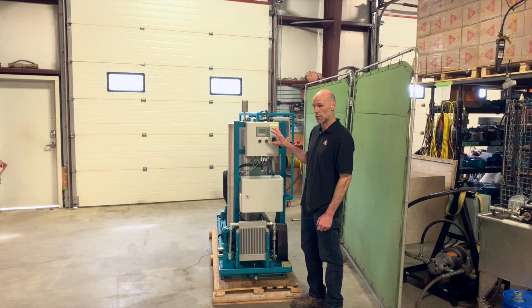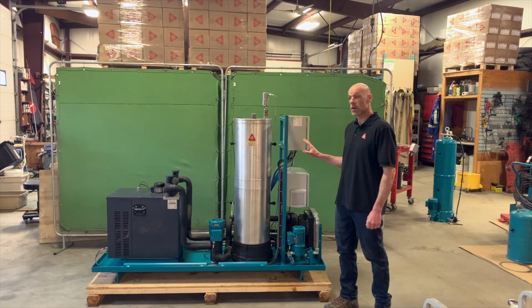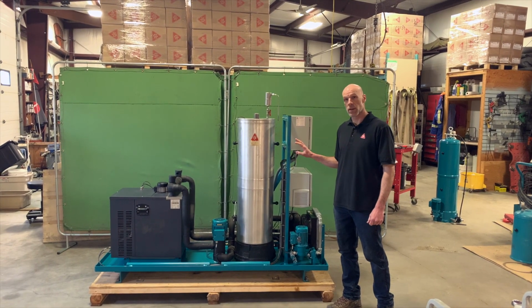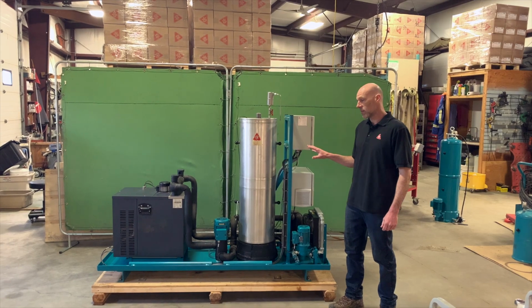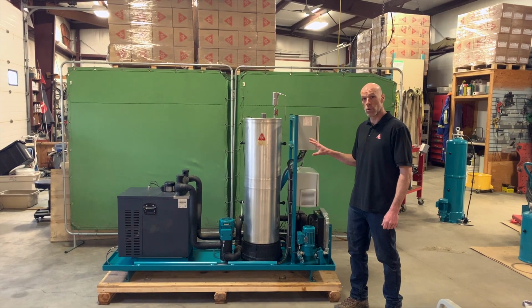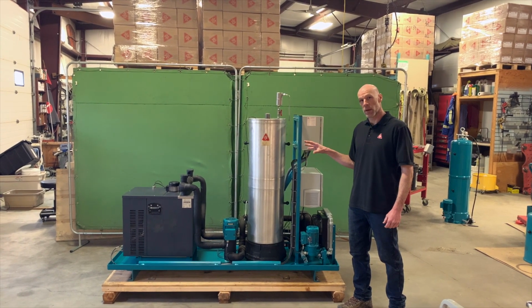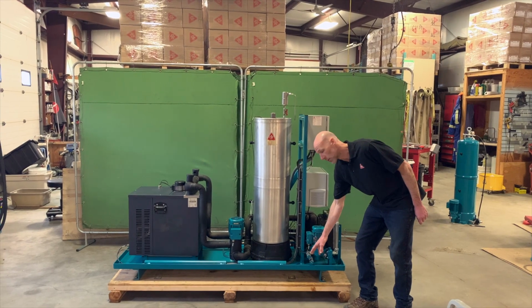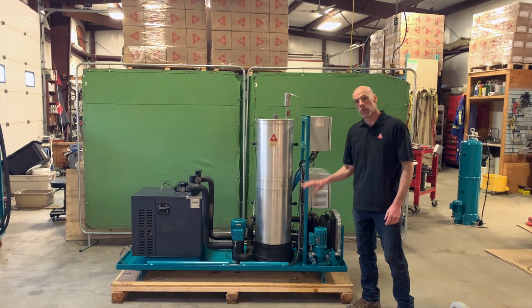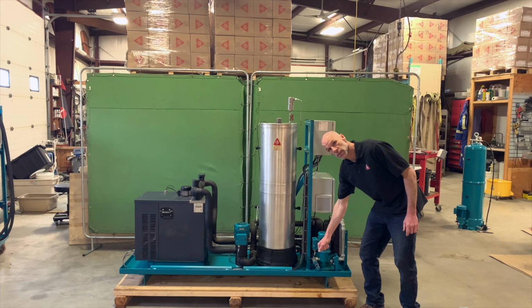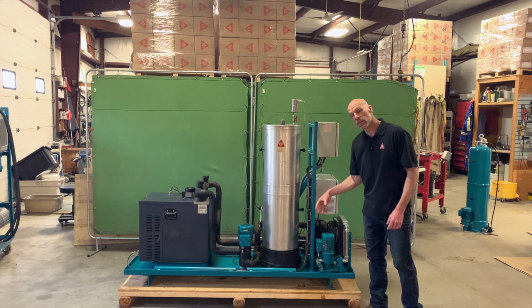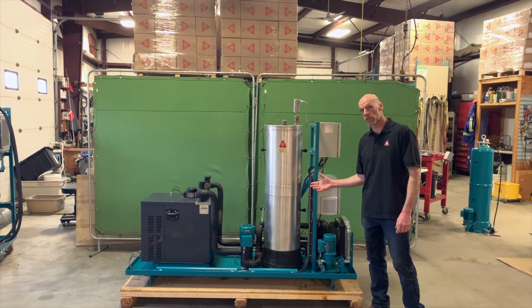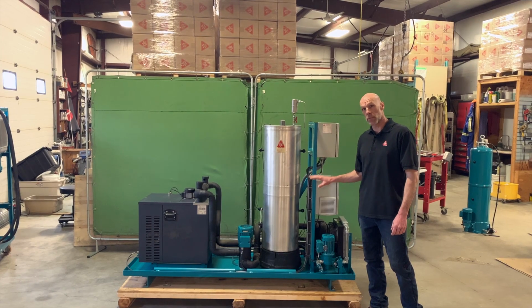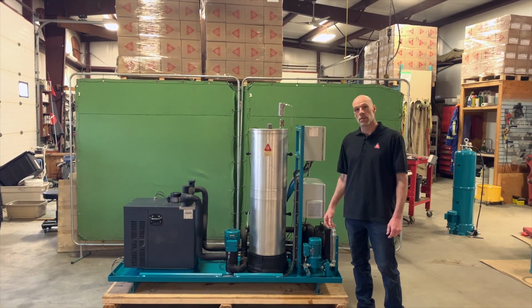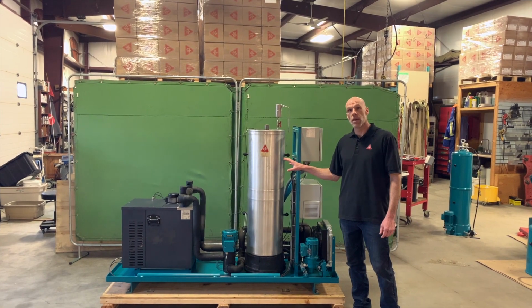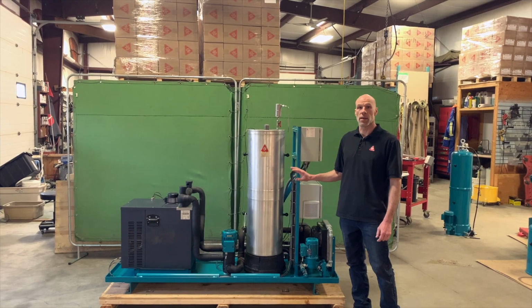If you're taking down the VRU to perform a filter change or any maintenance on it, it's important to make sure that when you turn it off, it's not cold, so let it warm up to room temperature before isolating from a system using any valves. If you turn it off when it's cold and shut the valves on the inlet and the outlet, as the temperature rises, the pressure is going to increase. So be sure that it warms up before shutting any valves. Once the unit is back to room temperature, then you can isolate from the main system and proceed to perform the maintenance.